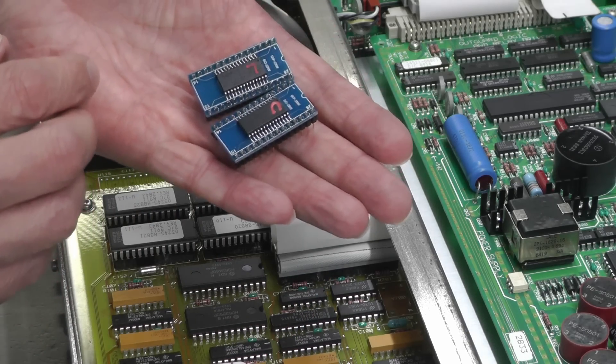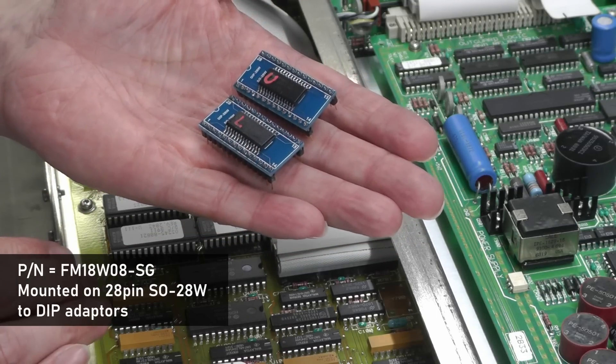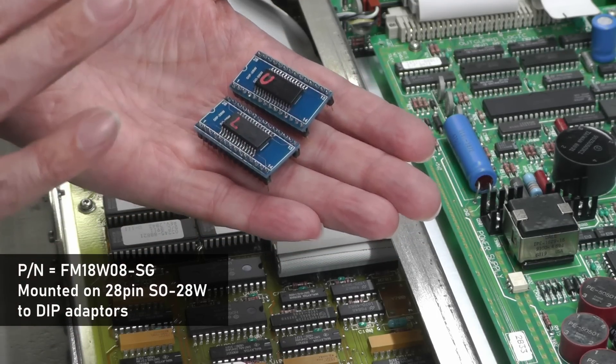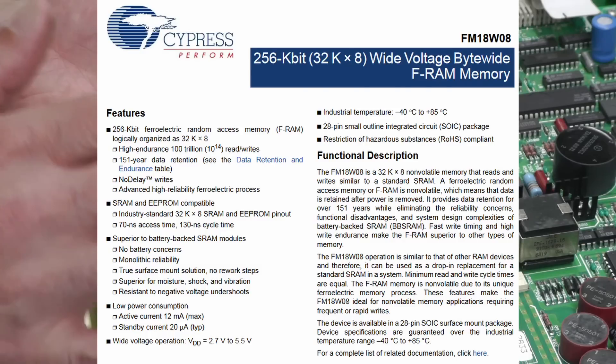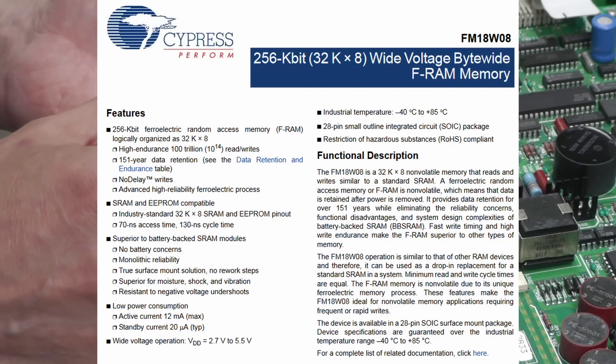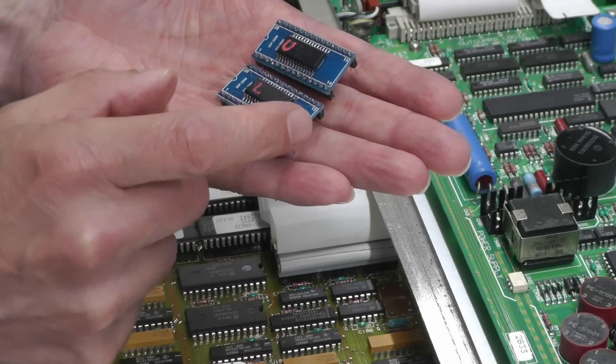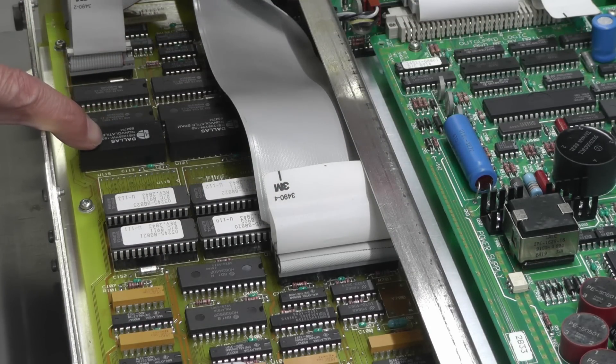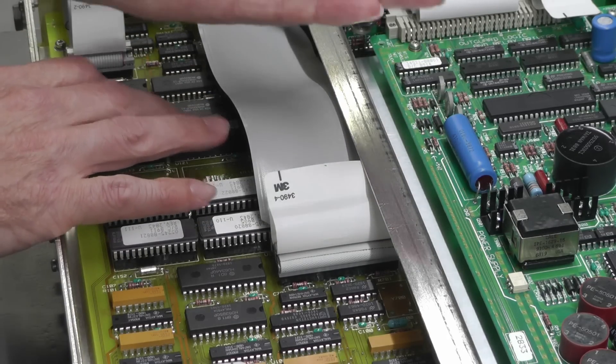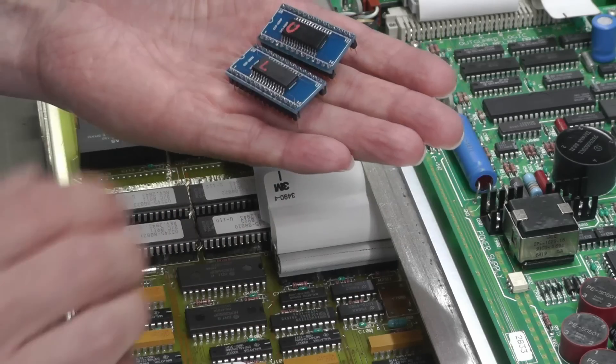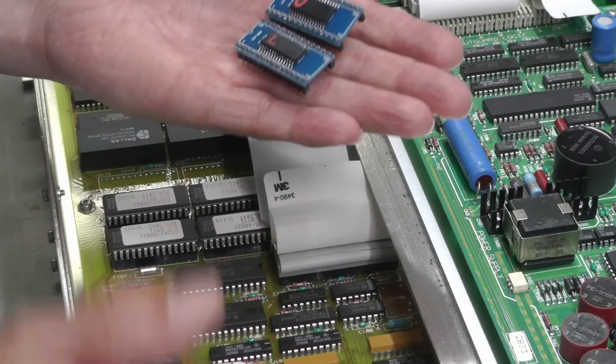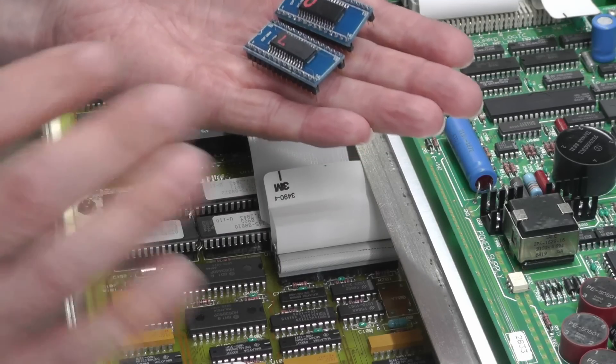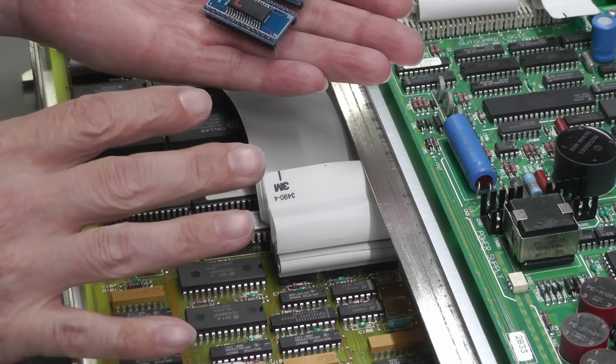I'm not going to change them out for exactly the same types of units. I'm actually going to use a new technology, or new to the 3245A anyway. I'm actually going to change them out for these—these are a couple of FRAM non-volatile RAMs. The good thing about these is there's no batteries, no external power supply at all required. And luckily, just by using a couple of SO to DIP adapters, you can basically create exactly the same footprint as the original Dallas RAMs. So it's just a case really of unplugging those and plugging these in, then powering it up, clearing the errors on the display, turning it off, turning it on again, and hopefully we shouldn't have any more errors.